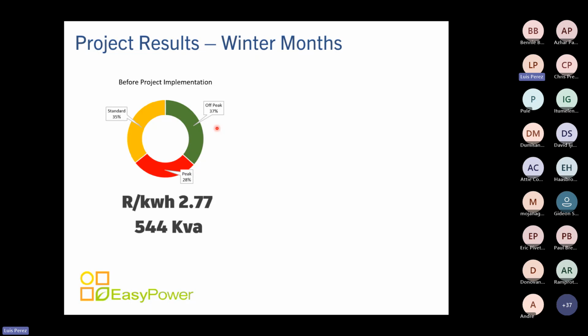With these customer tariffs, which are about to increase a whole lot, as you've seen on the previous slides, that represents an average cost of 2.77 rand per kilowatt hour, excluding demand charges and fixed charges, with a peak demand of about 544 kVA. Now, after the project implementation, we've moved from 37% off-peak to 56% off-peak. And remember, this is a tailored approach. We are only offering the size of solution that will pay for itself in the quickest possible time. So the peak energy has reduced from 28% to 10%, and your standard energy remains more or less the same because our PV system is mostly used to recharge a battery.